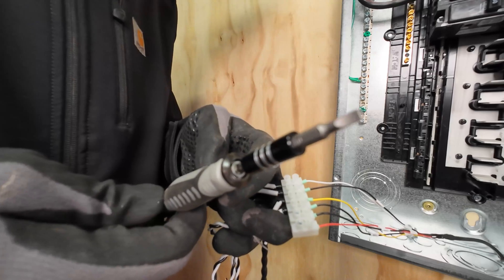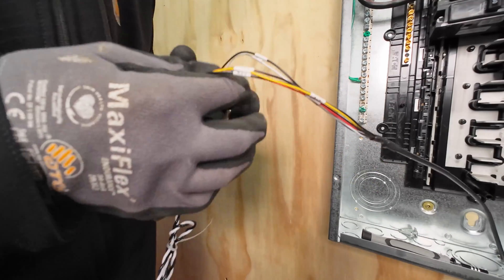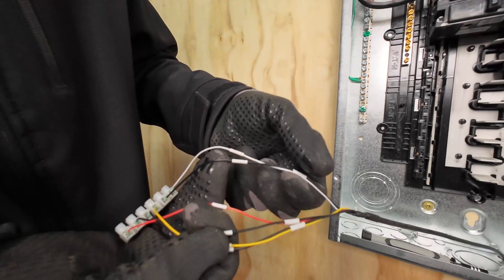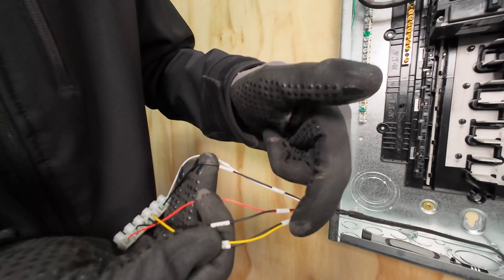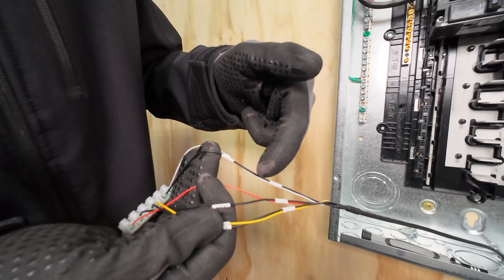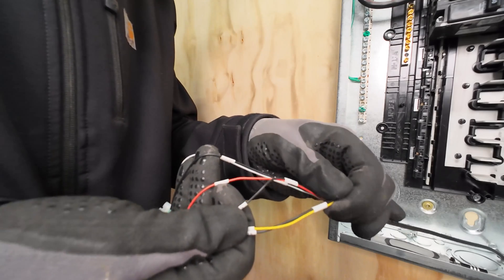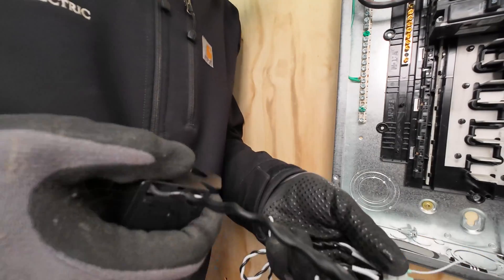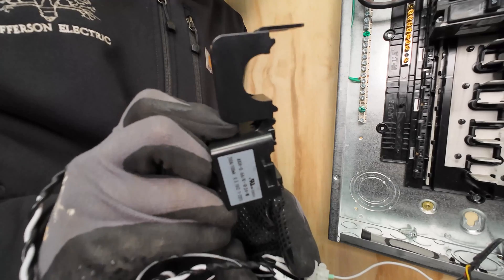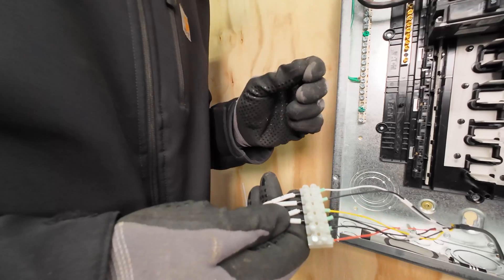To do this installation, I used a 3 millimeter flathead screwdriver and it worked great. Each one of these leads is labeled. They come in groups of two — there are a total of three groups of two. I'm only using two sets of conductors today. That third set is for L3, line three in a three-phase system, which I will not be using. If you do need an additional split core CT of this exact specification, Fulcelin has it available on their web store. Now that I've tug tested all of my terminals, I'm ready to install my CTs on the lines.